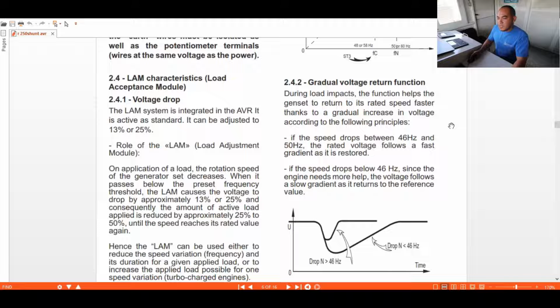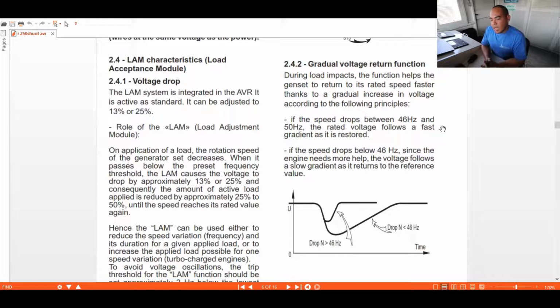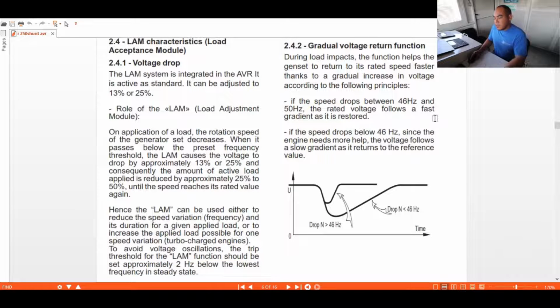So the LAM is not only helping the impact load, it is also helping the frequency to recover as fast as it can. Here, during the impact load, the function helps the generator return to its rated speed faster thanks to the gradual increase of the voltage according to the following principle. If the speed drops below 46 Hz, since the engine needs more help, the voltage follows the gradient as it is restored to the reference value.